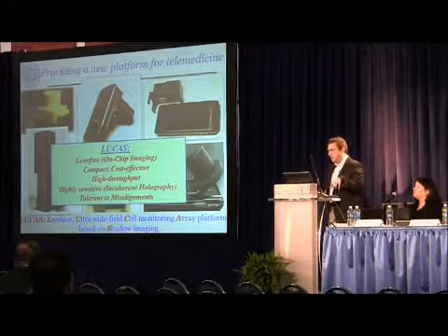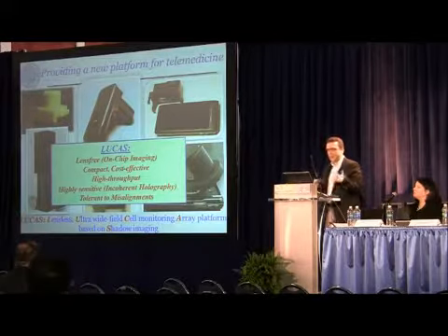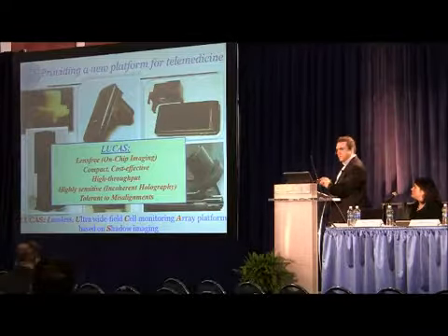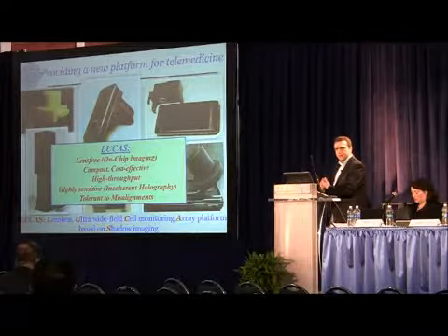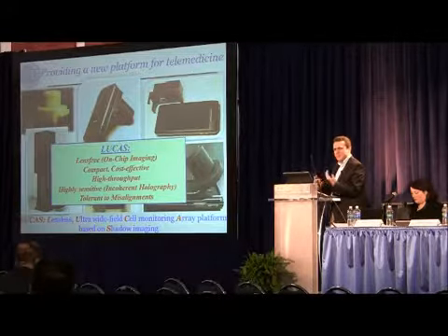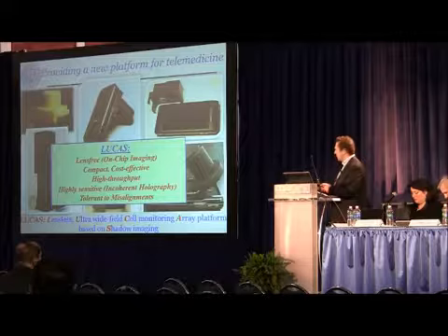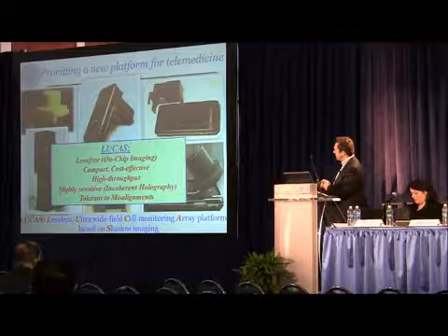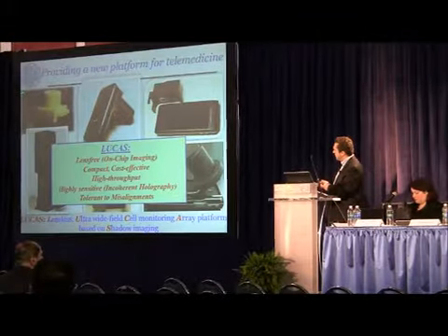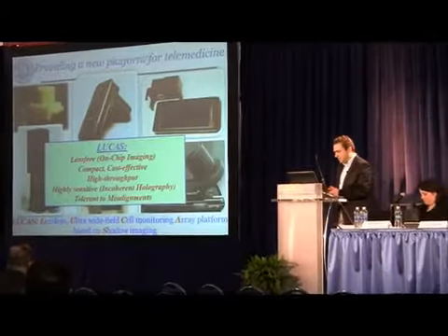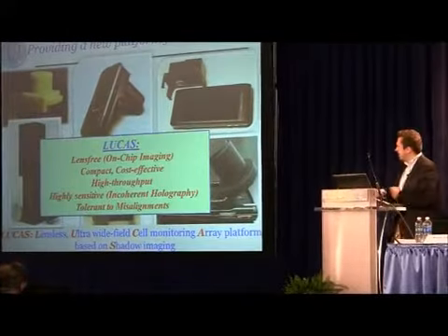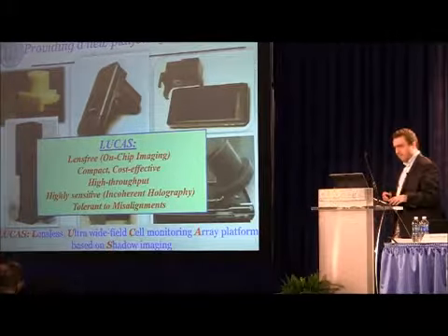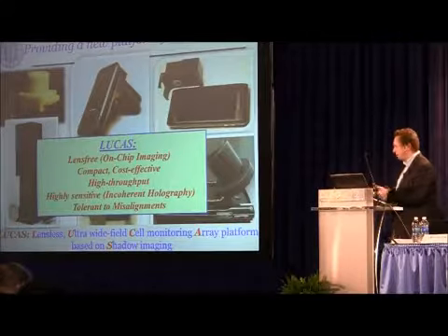So there are some key unique features of this platform that make it quite different than a conventional microscope, in the sense that, first of all, it's a lens-free technology. We use computational algorithms to make up for the lack of complexity, because there is not any lens or bulky optical components involved in these microscopes. As a result of that, they're quite compact, as you can see. This attachment to the cell phone is on the order of 40 grams. This standalone unit microscope or this one are both less than 100 grams. And that's why it becomes easy to put them together and carry around if you are a field worker, for instance, in a remote location.